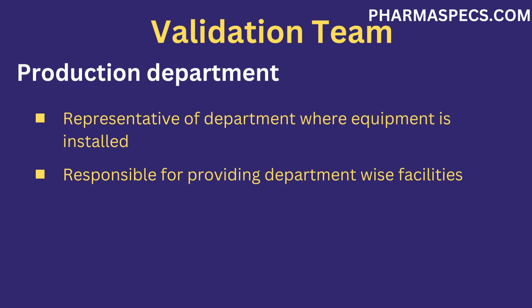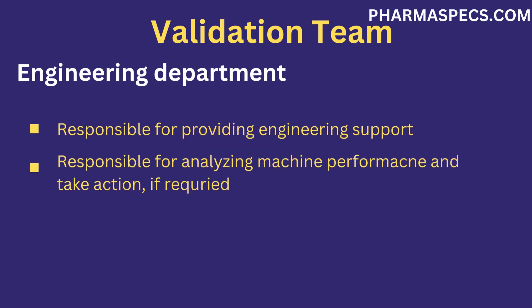A representative from the production area where the equipment is installed must be present during the validation activity. The production personnel are responsible for providing production-wise facilities such as arranging equipment, product, or packaging material. The engineering department is responsible for providing engineering support, analyzing the machine's performance, and taking action in case a fault occurs.